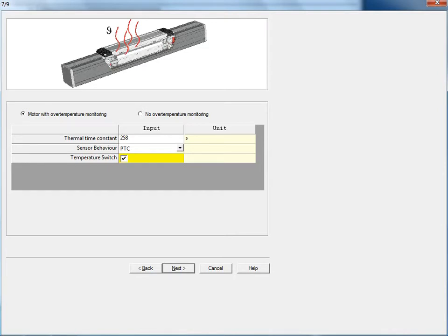The motor thermals are actually used to calculate and estimate what the winding temperature of the motor is. So the thermal switch is actually a backup protection device to the thermal model. Now with the 24 volts, it's powering up the logic, and it's monitoring what the continuous current going to the motor is and the peak current, how long it's operating. So it's estimating what the winding temperature is, and will actually shut down faster than the thermal switch.